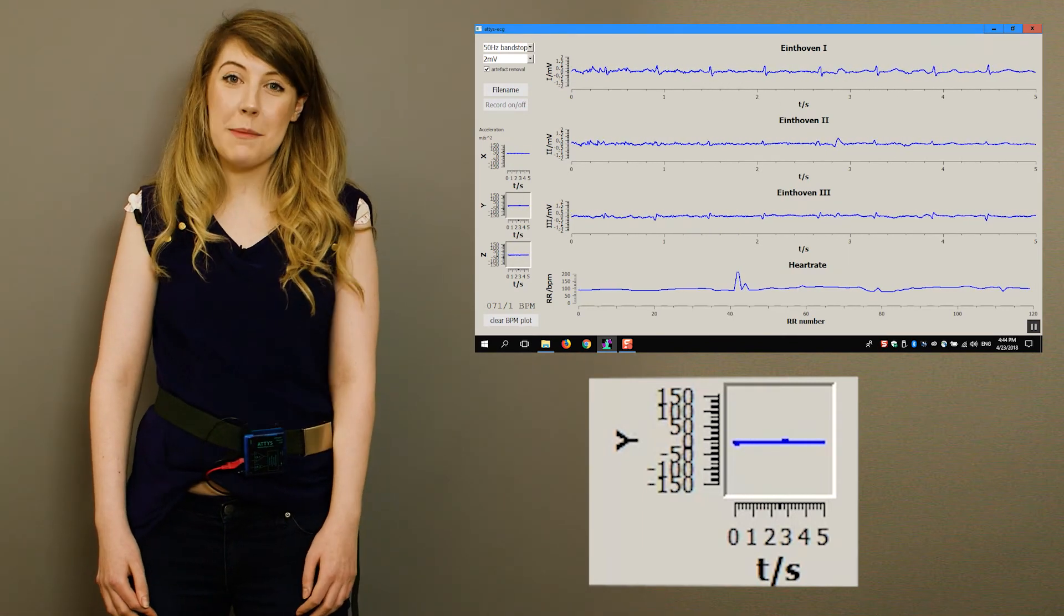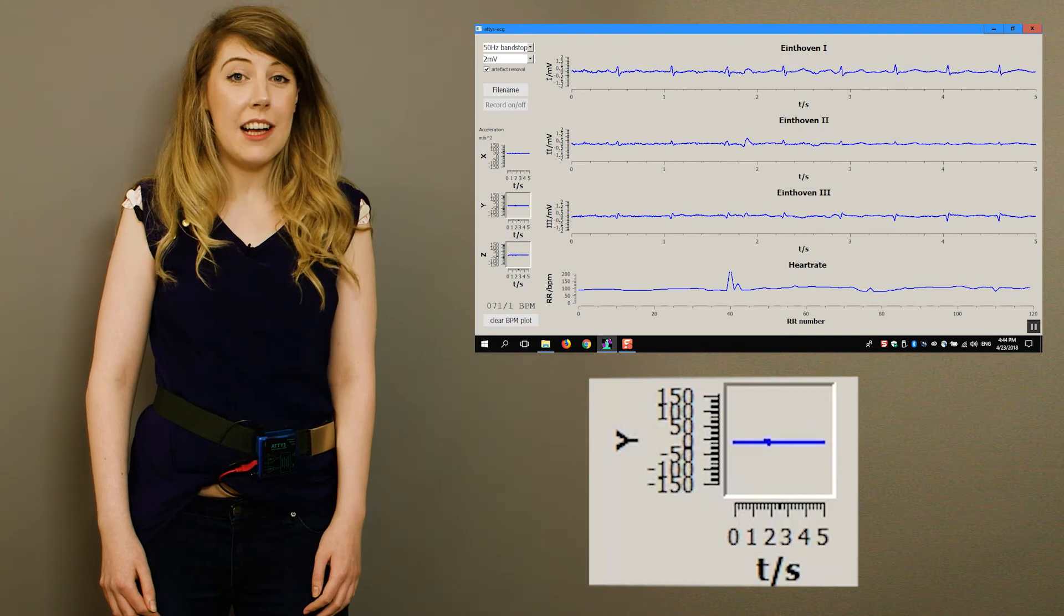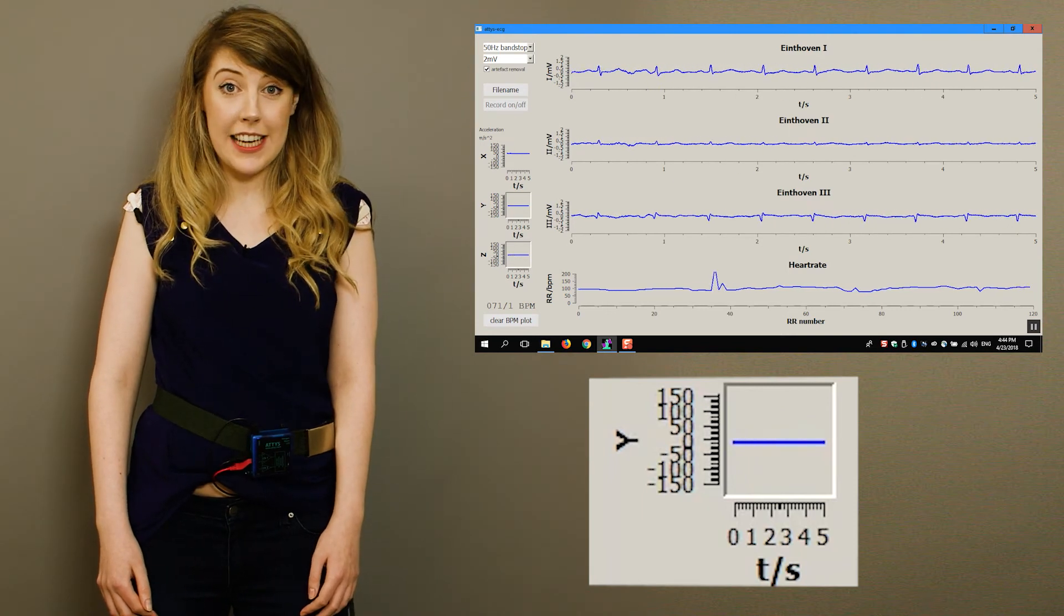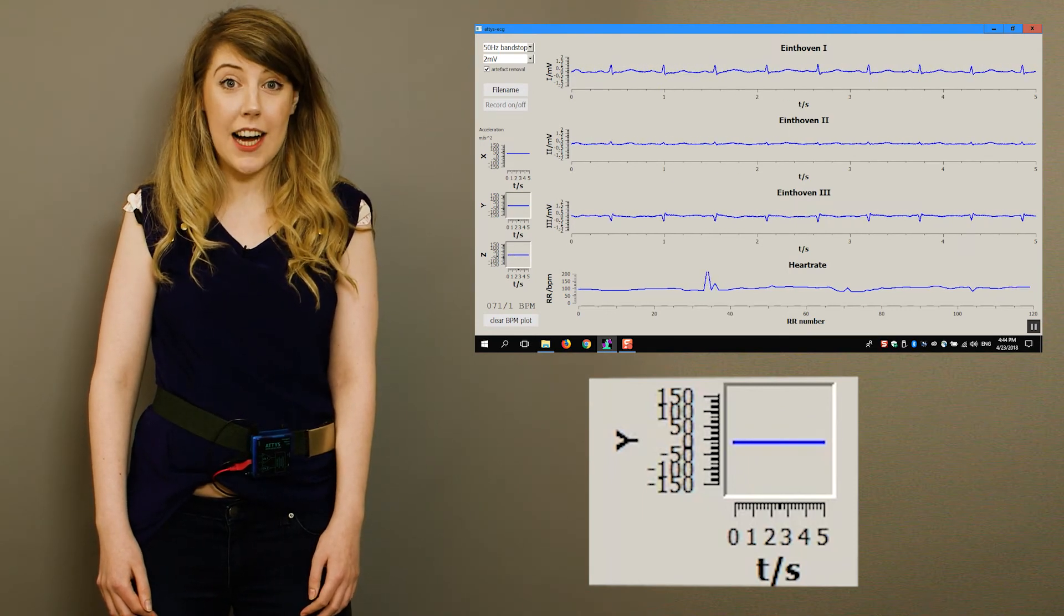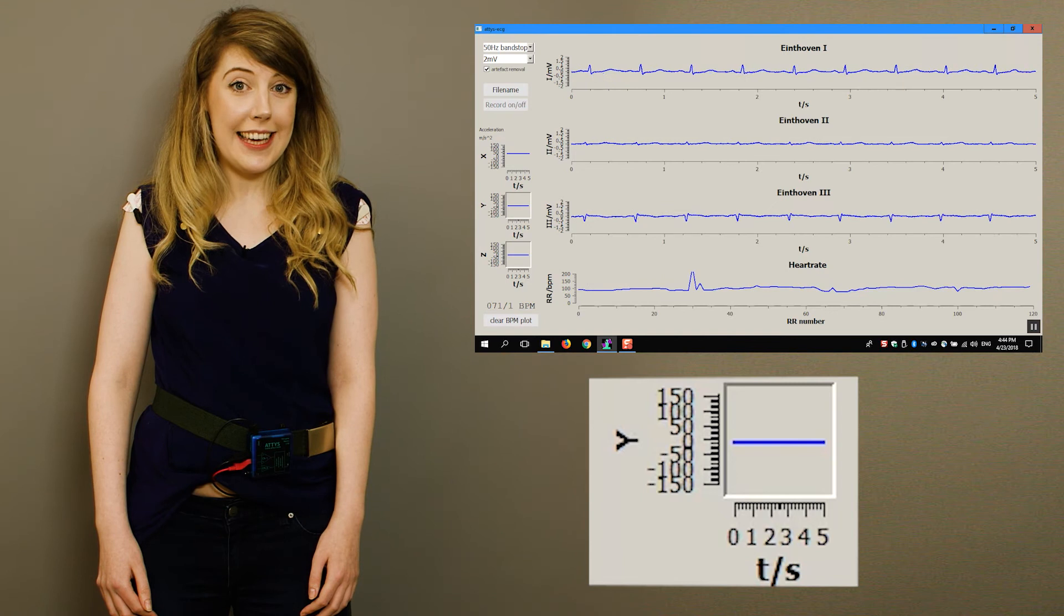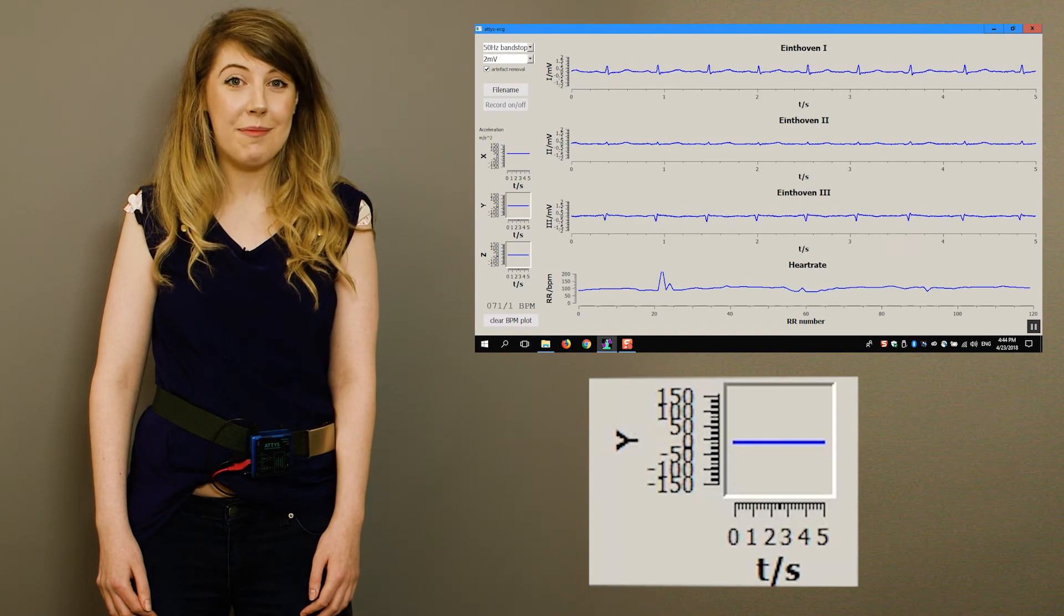In summary, avoid any muscles between the electrodes and the heart and make sure the cables cannot move.